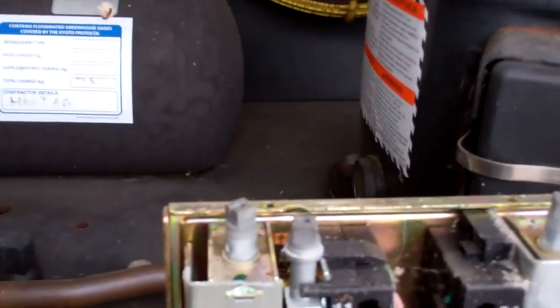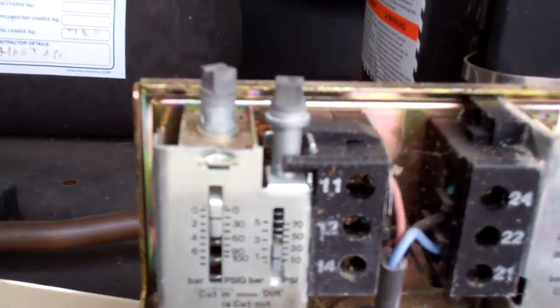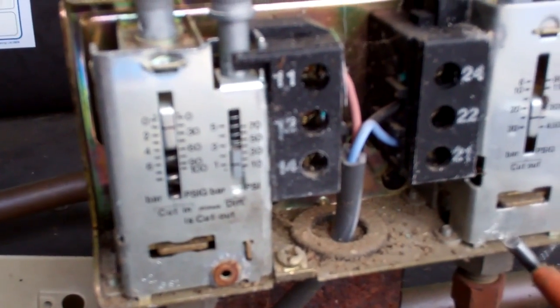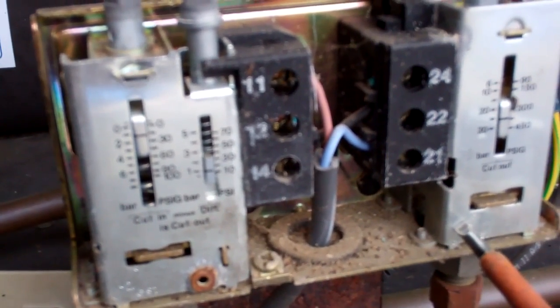Right, I've got to cover off the other switch on this one. This one is obviously white. The HP's on this side and the LP's on this side. And that is something to be very aware of if you're changing these for different makes and models.